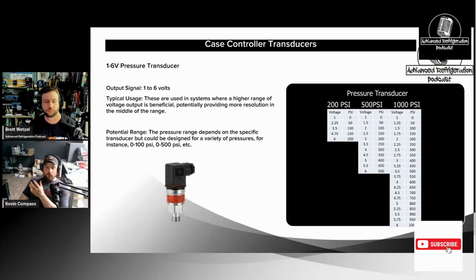Now let's go over a basic one, we'll say a Copeland style or Danfoss style, where we're reading DC voltage at an input. So what we're going to do is take 5 or 12 volts, whatever's powering that transducer, and it's going to go into the transducer. This is a 3-wire connection: you've got power in, you've got a ground wire, and you've got power out, meaning your signal input.